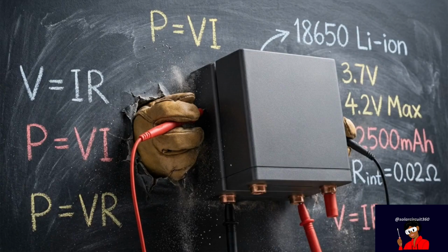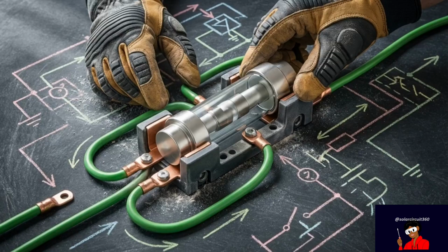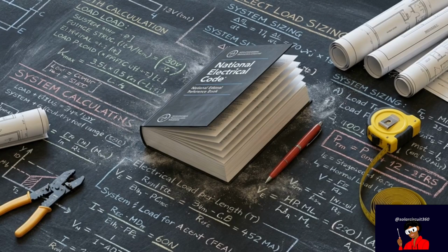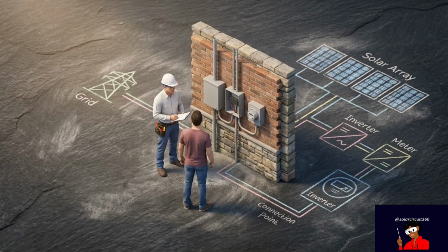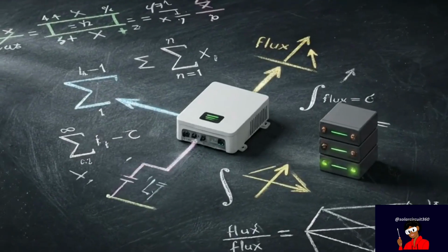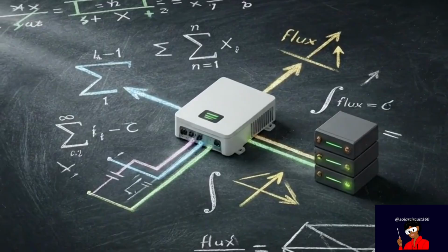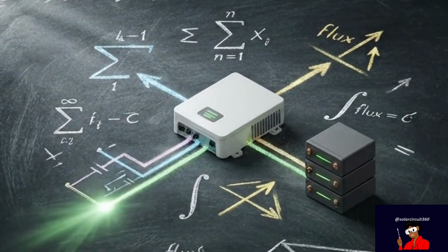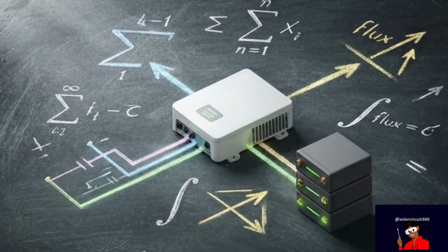Before powering up, verify your battery sizing, install properly rated DC fuses, and physically resolve all grounding topologies. Executing this math requires strict adherence to local electrical codes. You must consult a qualified professional before initiating any grid interactive connection. A hybrid inverter provides a unified energy management platform, but its utility depends entirely on respecting these strict physical limits.